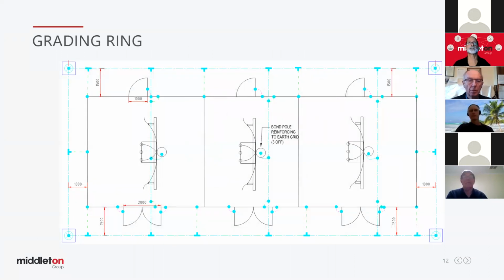So here's an example of a set of 3 transformers, pole mounted, sectioned off in their own fenced areas with a man-proof fence, and a bunch of gates for access for maintenance, of course. In this situation, it's a hypothetical, but the public could potentially be exposed to the voltages on the external fence should there be a fault at one of these transformers. You'll get an EPR, you'll get touch voltages on the fences.